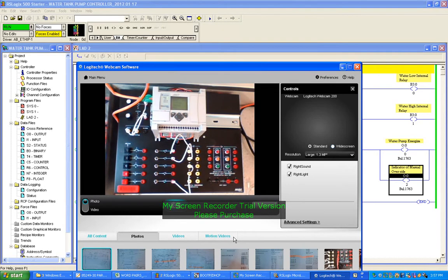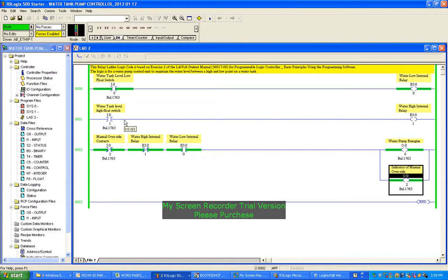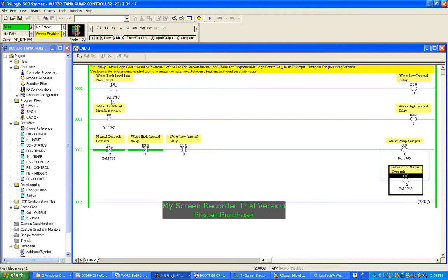When you are throwing those switches you should see a little green highlighting in the ladder logic. Water level low activates this contact, throws that coil, which energizes everything - since this contact is closed it energizes and turns the pump on. So you can really see the visual logic process occurring. Now there's a bit of a problem with this program. This is the low level switch - as soon as the float switch turns off, the pump turns off. So the pump is just going to go on, off, on, off, on, off like this, and we want to build up a reserve of water. So the high level switch is really redundant in this situation.